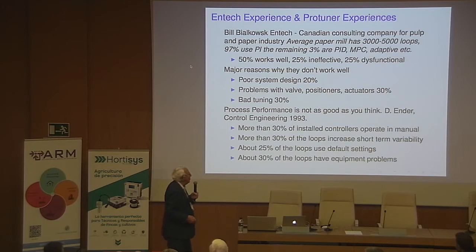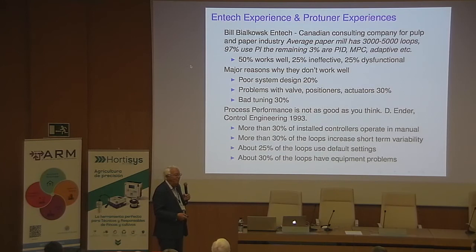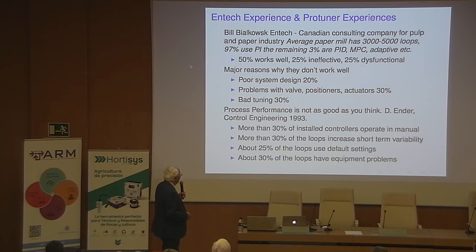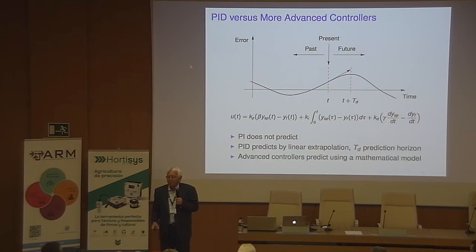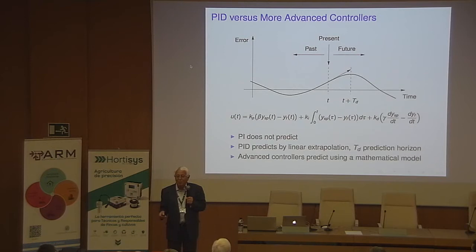A summary of how controllers behave: more than 30 percent of installed controllers operate in manual mode, so they're not even doing control actions. More than 30 percent increase short-term variability. That indicates clearly the need for tuning. Regarding PID versus more advanced controllers: a PID controller predicts by linear extrapolation of the output a little bit forward, whereas an advanced controller predicts using a mathematical model.